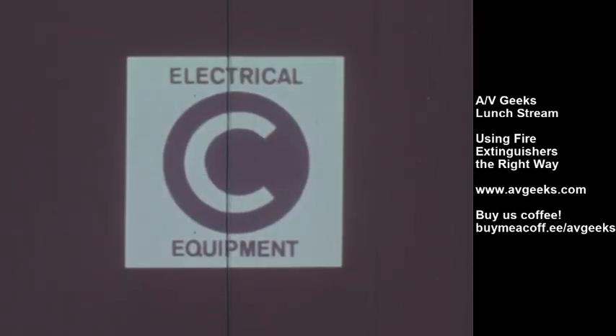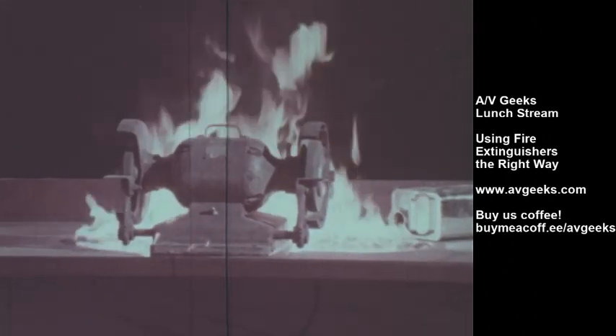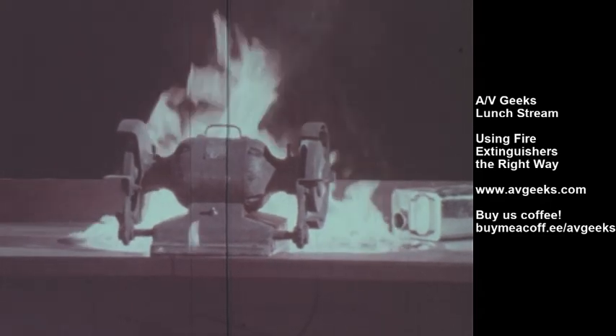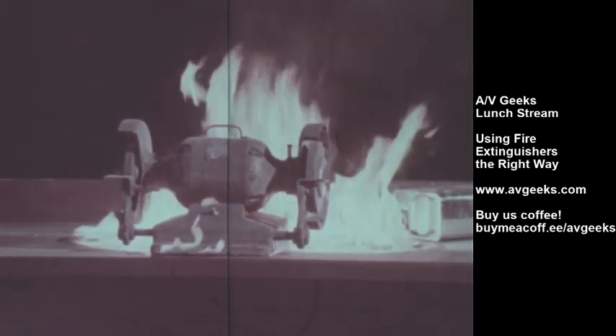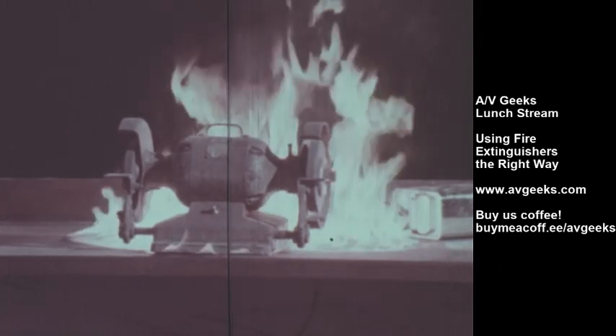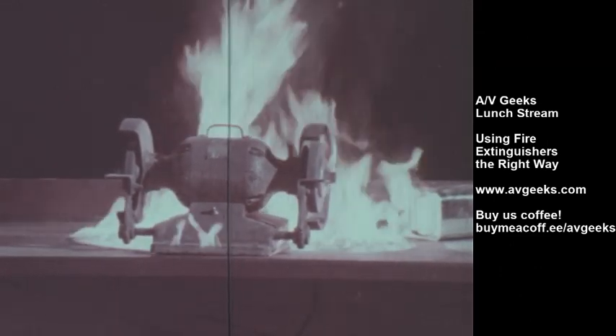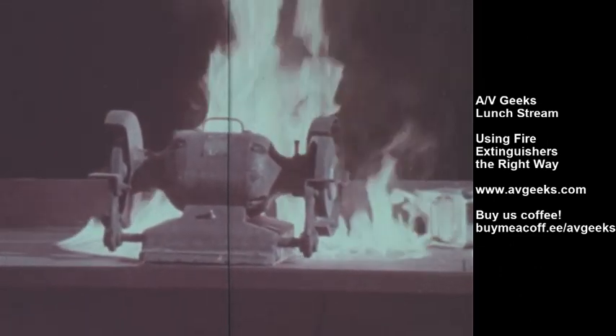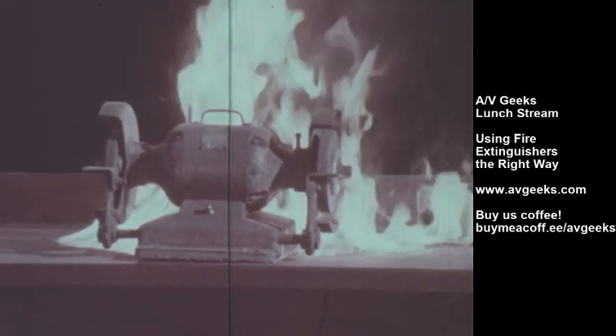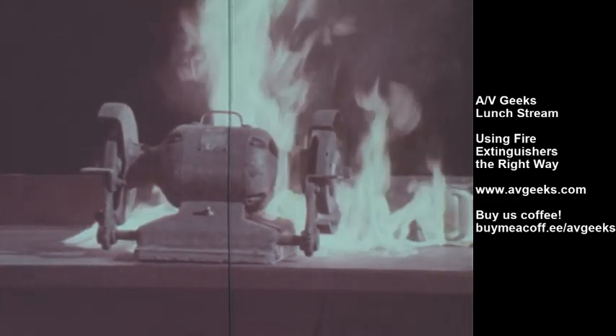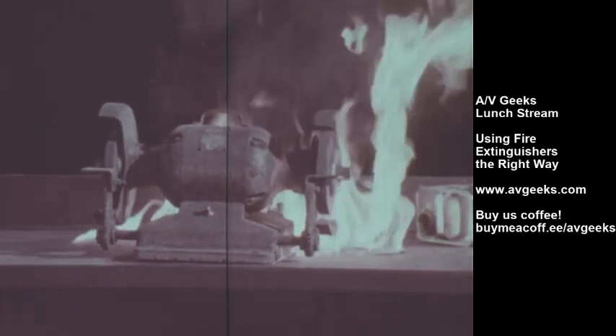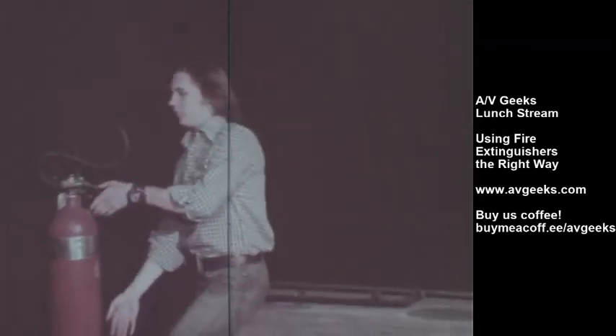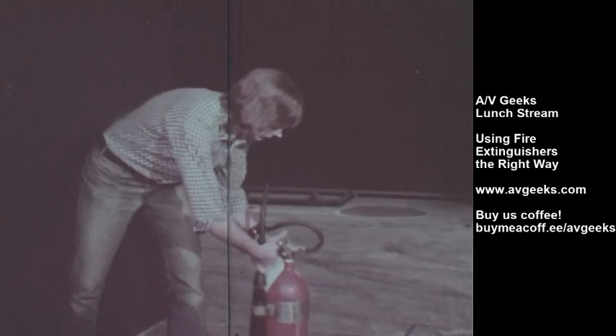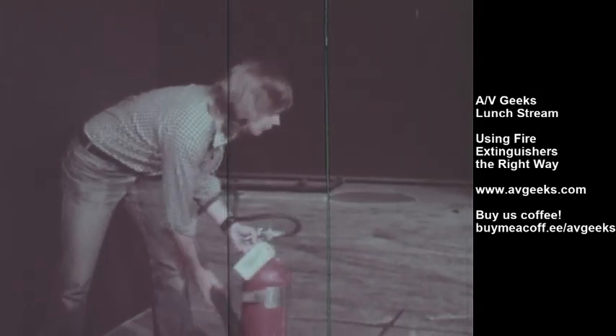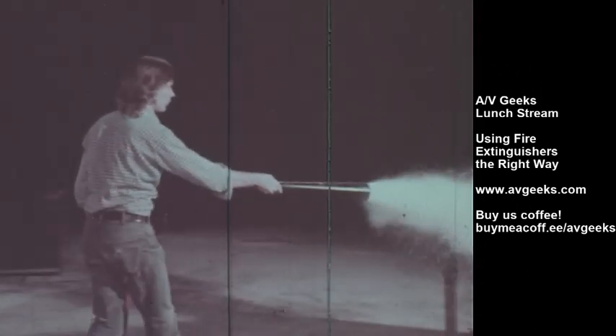Class C fires involve energized electrical equipment. This poses special problems because of the dangers of electrical shock while fighting the fire. Extinguishing agents must be non-conductive, so you should not use water on a fire in or around live electrical equipment. A common extinguisher used on live electrical fires is the combination BC carbon dioxide or CO2 extinguisher, easily identified by the cone.